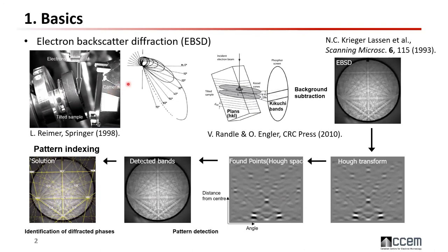The reason we tilt the sample to 70 degrees is because we want to yield a high number of backscattered electrons. Regarding the physics of EBSD: your electron beam arrives on your sample surface and is initially scattered in all directions, but only those electrons matching the Bragg diffraction condition are scattered coherently onto your EBSD camera to form the Kikuchi bands. The bands originate from the lattice planes, and all intersecting planes form this EBSD pattern.